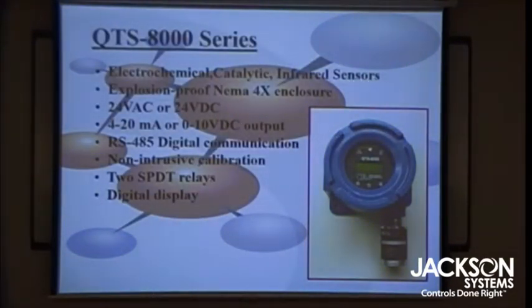But with a non-intrusive device like this, we actually give you a magnetic pen, and you go through the menu for the gas. So you go up, down, accept, move ahead. So you never have to open it up, so you don't have to go on downtime. And you can actually take the unit offline so that you calibrate, to make sure that it's doing its full span. You're not turning a whole bunch of alarms on, so you go into calibrate mode to shut down all the outputs.